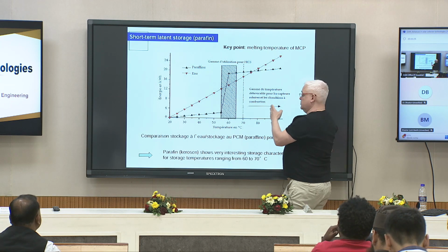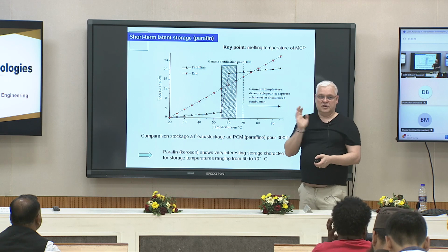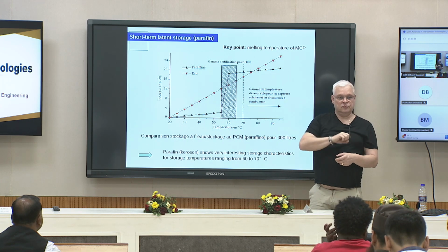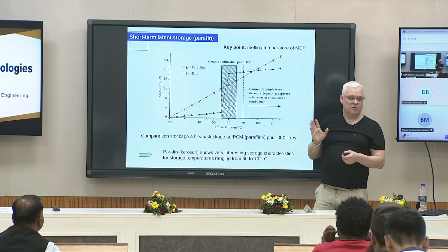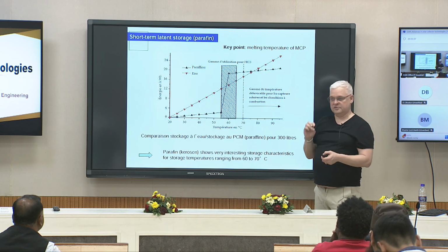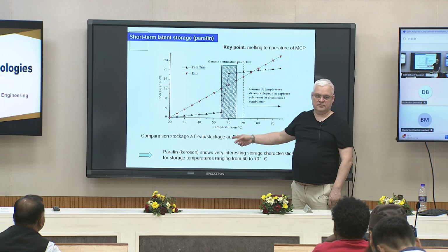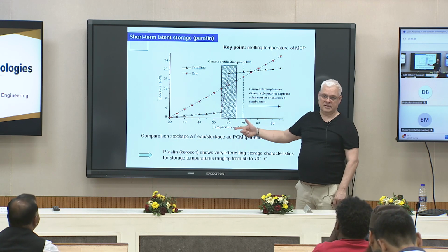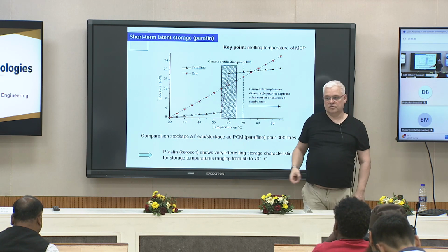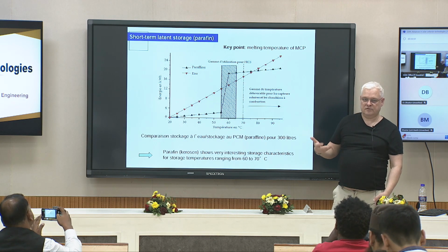So an important remark is that it's not because you are changing from sensible to phase change material that you will be more efficient. You have to be very cautious about the choice of the temperature. And it is the main issue generally in the application. People speak a lot about phase change material being beautiful and so on.